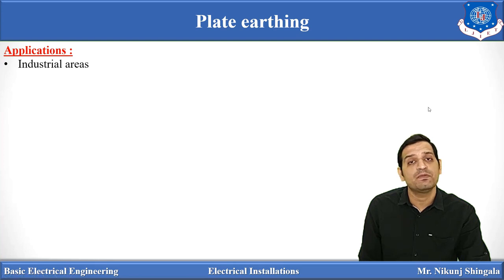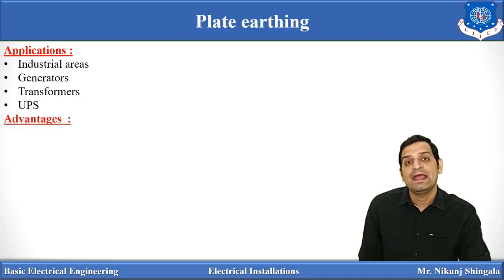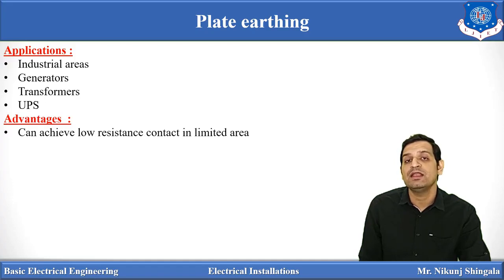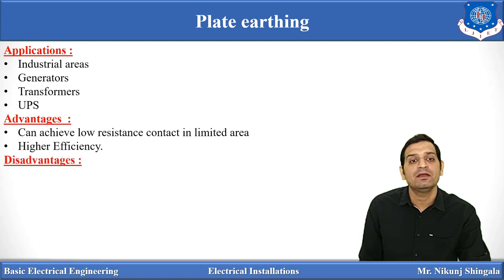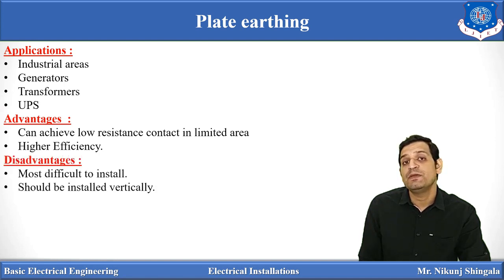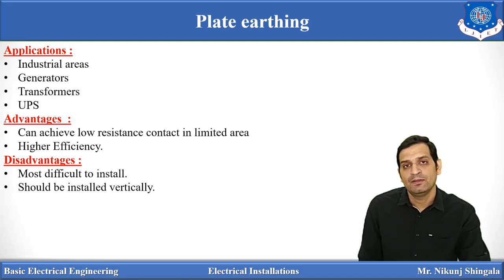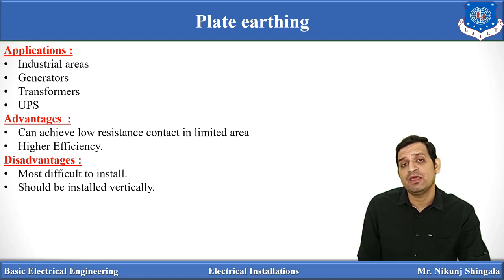Plate earthing is basically used in industrial areas, for generators, transformers, and high voltage applications. It is also used in UPS systems. The advantage is that it can achieve low resistance contact in a limited area, and it has higher efficiency compared to the pipe earthing method. The disadvantage is that it is difficult to install and should be installed vertically. The choice between pipe and plate earthing depends on the type of application and voltage being handled.